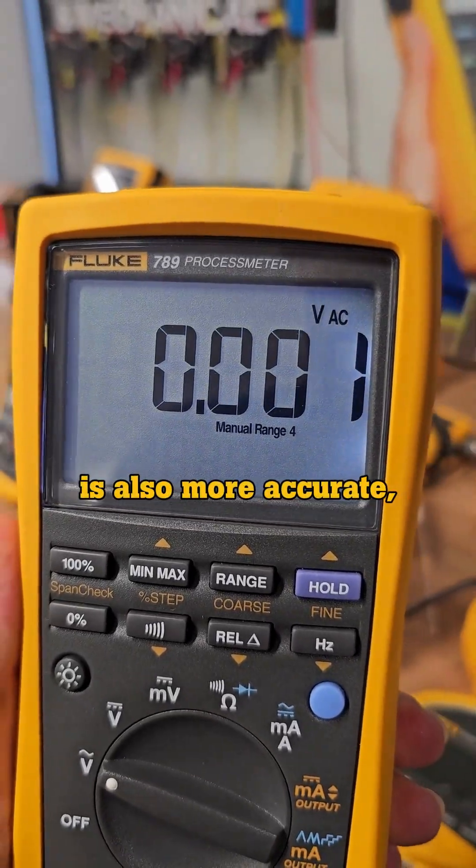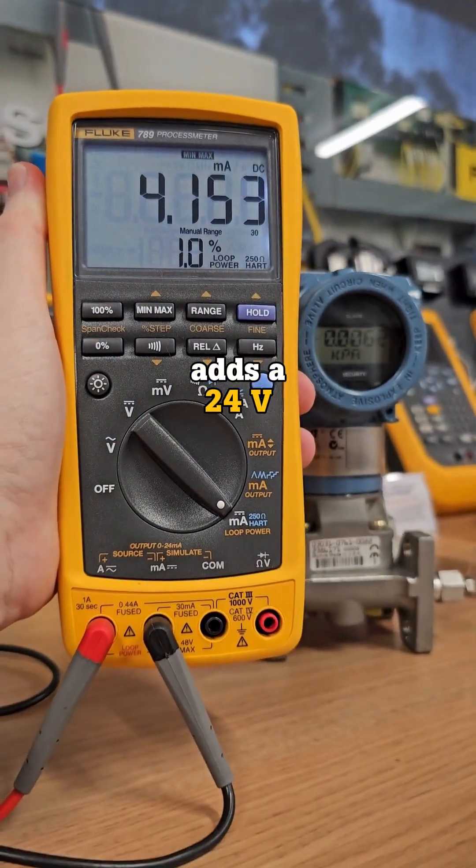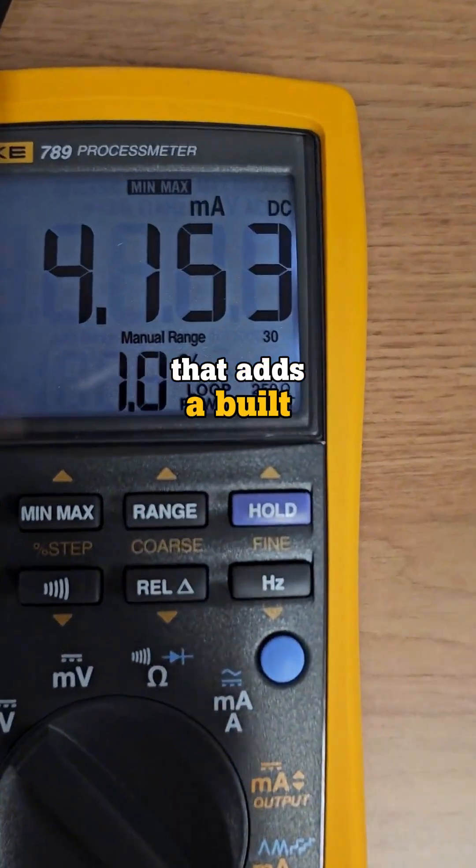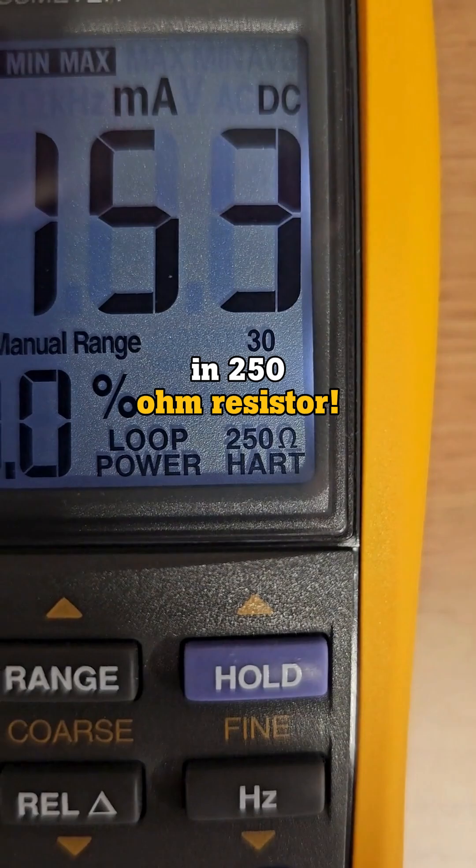The Fluke 789 is also more accurate, adds a 24V loop power supply and a HART mode setting with loop power that adds a built-in 250 ohm resistor.